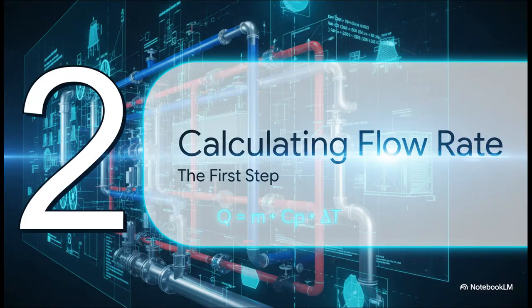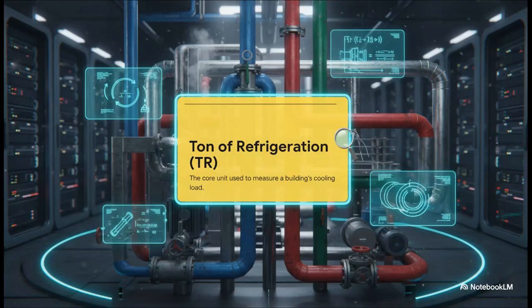All right, so where do you even start with a design like this? Well, the very first step is always to figure out exactly how much cooling the building actually needs. That number tells us how much water we need to get moving. And to measure that cooling, we use a unit called the ton of refrigeration, or TR for short. Just think of it as the fundamental unit of cooling power. It's the target we're aiming for.